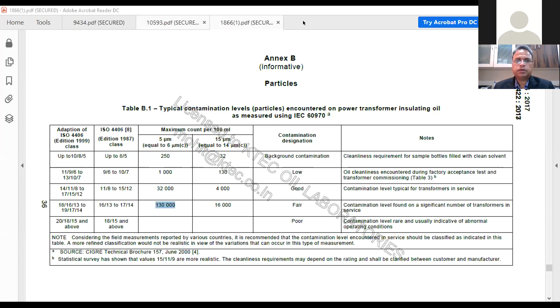So these are the categories actually. It depends on the number of particles that you are getting in your analyzer. There is an instrument like a particle count analyzer. The sample is passed through that analyzer, and using a laser beam, it detects the size of the particles and the quantity also. If you are getting these particles, you need to refilter and again recondition the transformer. Okay, thank you.